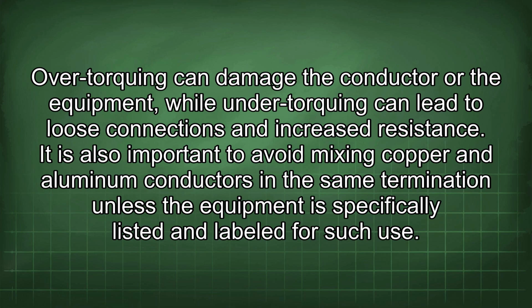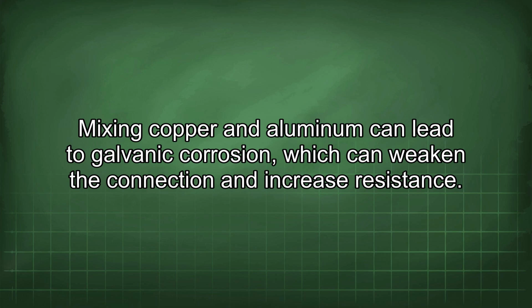It is also important to avoid mixing copper and aluminum conductors in the same termination unless the equipment is specifically listed and labeled for such use. Mixing copper and aluminum can lead to galvanic corrosion, which can weaken the connection and increase resistance.